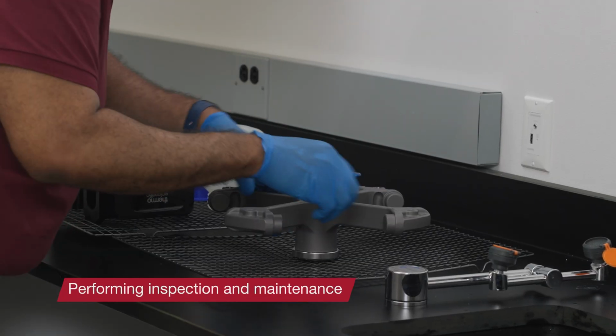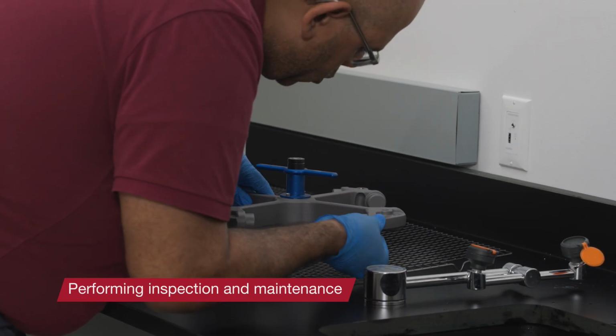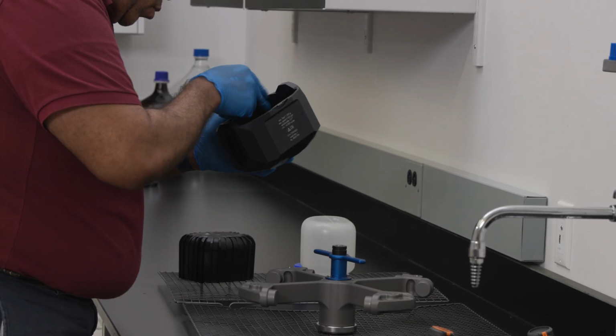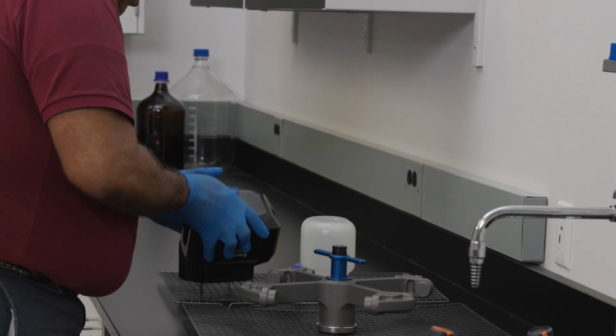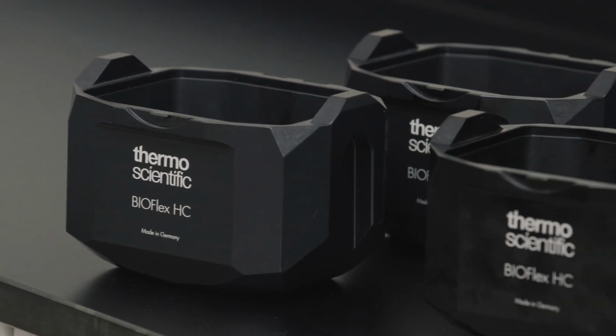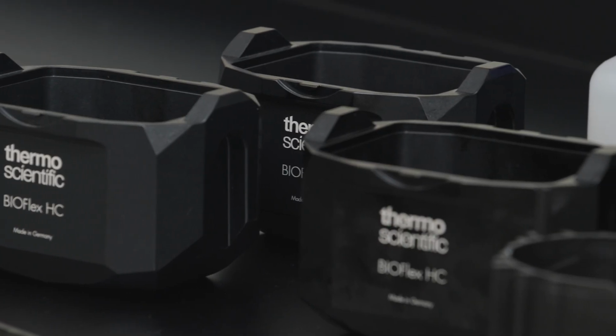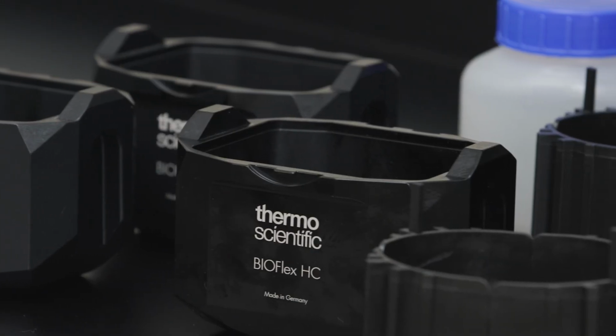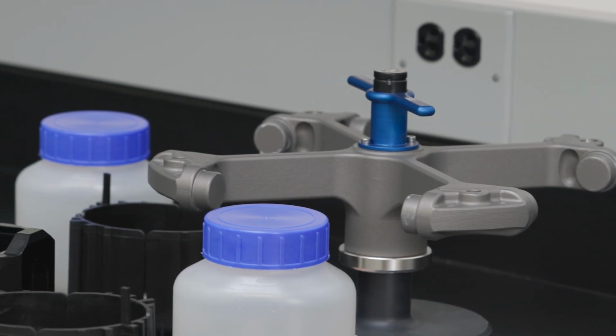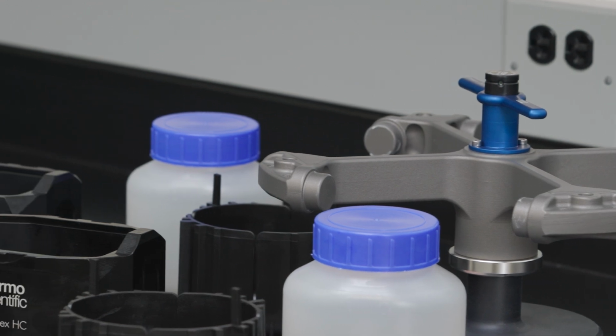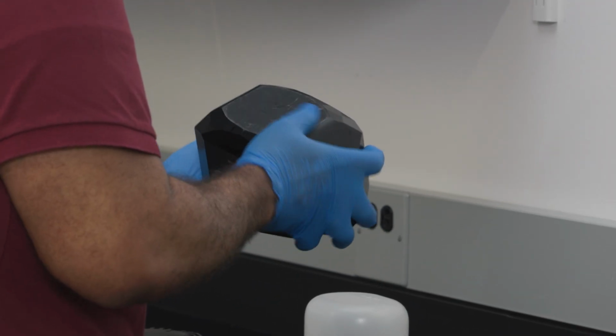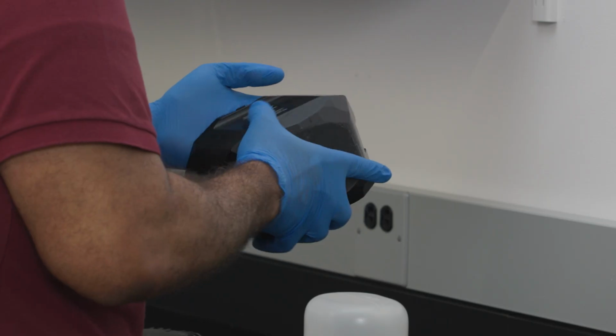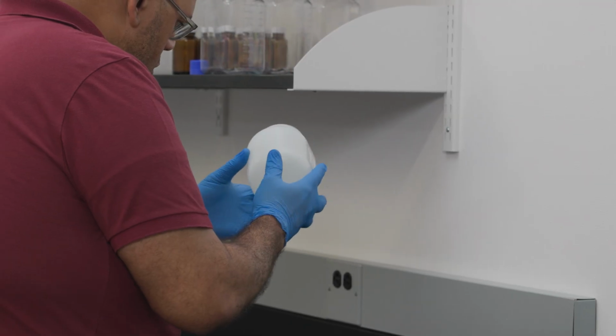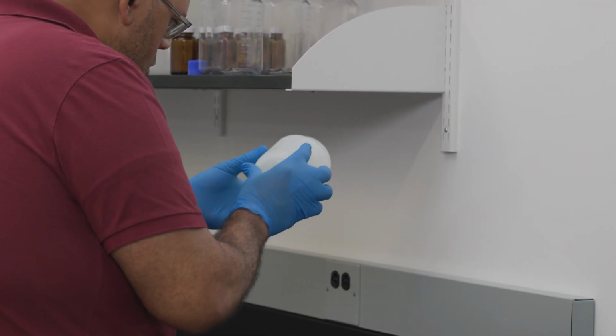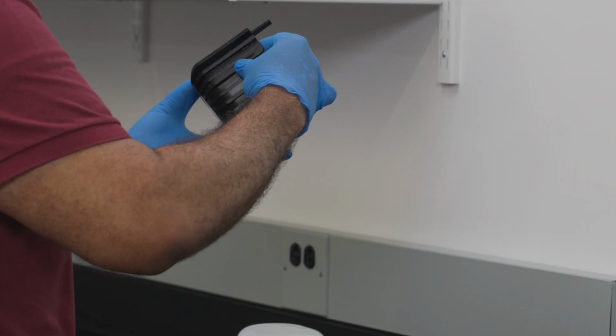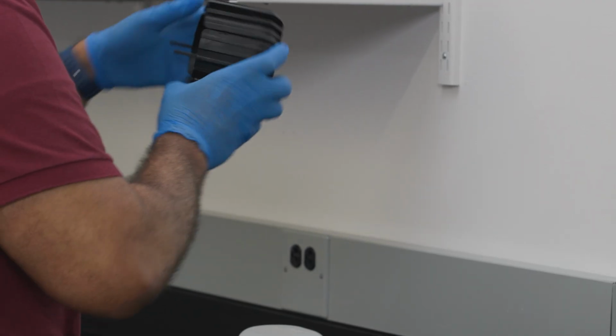After thoroughly cleaning the rotors, inspect for damage, wear, and corrosion. Do not run rotor or accessories with signs of damage. Ensure rotor, buckets, and accessories are within their expected maximum number of cycles. For safety purposes, it's recommended to inspect rotors and accessories yearly. Remove the metal parts with corrosion, such as rust or pitting, from service immediately. Also, remove items with plastic crazing, fading, bruising, or cracking from service, and replace brittle or damaged O-rings.